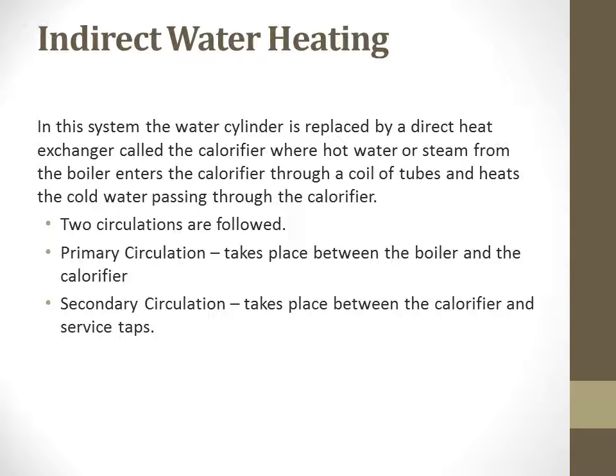Next is the indirect water heating system. In this system, the water cylinder is heated by a direct heat exchanger called a calorifier. Hot water or steam from the boilers enters the calorifier through a coil of tubes and heats the cold water passing through the calorifier. There are two circulations: primary circulation between the boiler and the calorifier, and secondary circulation between the calorifier and the service taps — the normal outlet taps that you use.